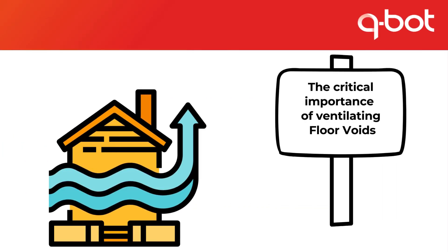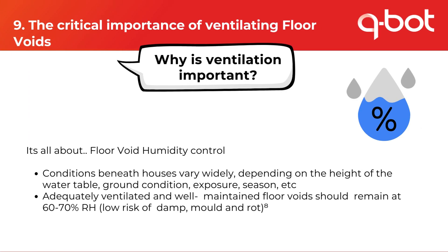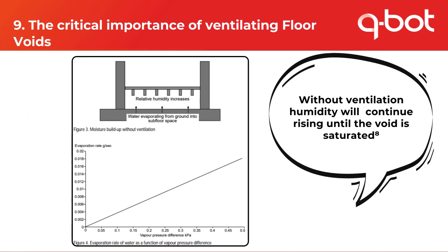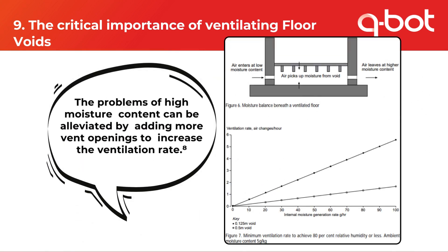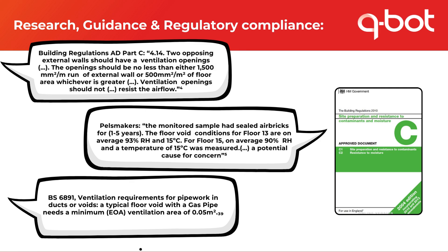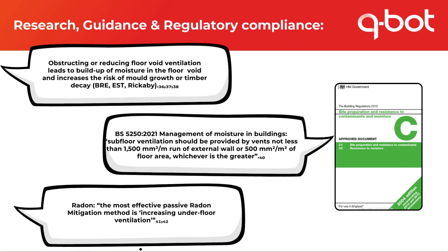The critical importance of ventilating the floor void is all about humidity control. Conditions beneath houses vary wildly depending on the height of the water table, ground condition, exposure and the season. Adequately ventilated and well-maintained floor voids should remain at 60–70% relative humidity. Without ventilation, humidity will continue rising until the void is saturated. Problems of high moisture content can be alleviated by adding more vent openings to increase the ventilation rate.